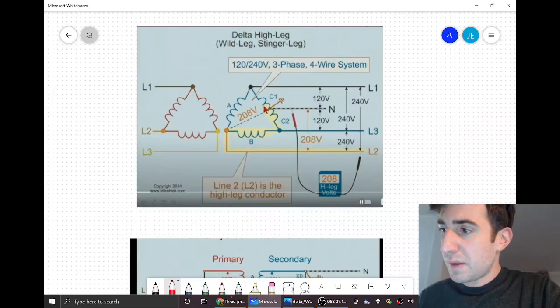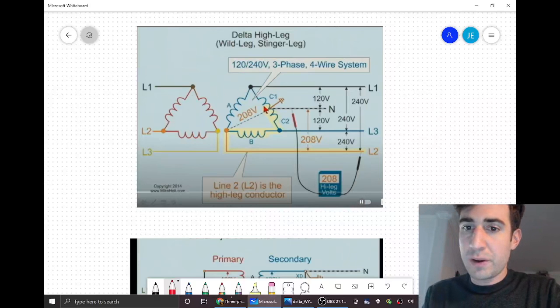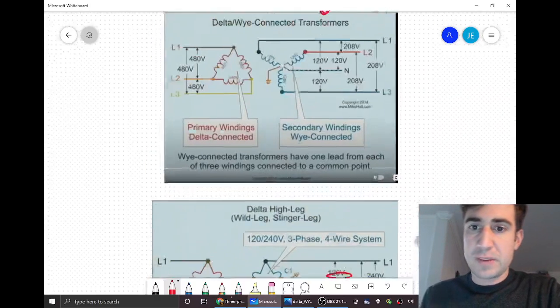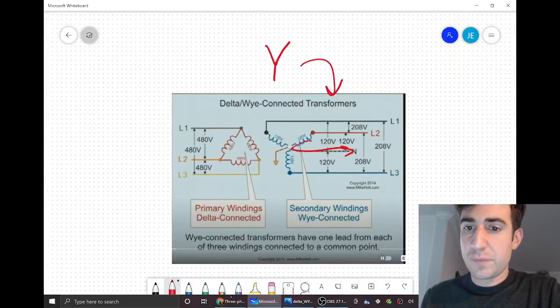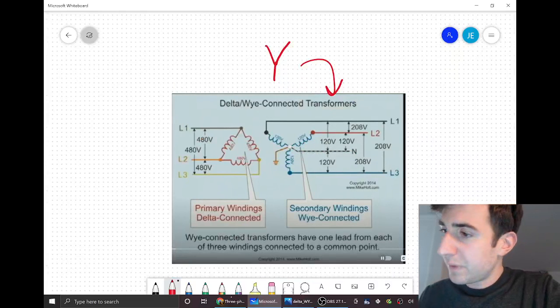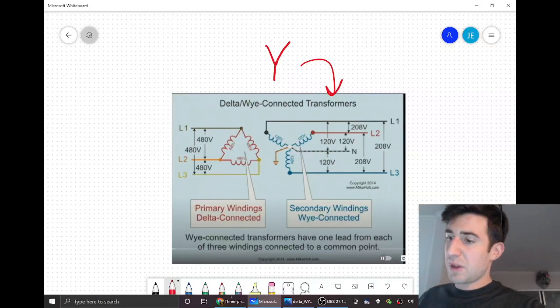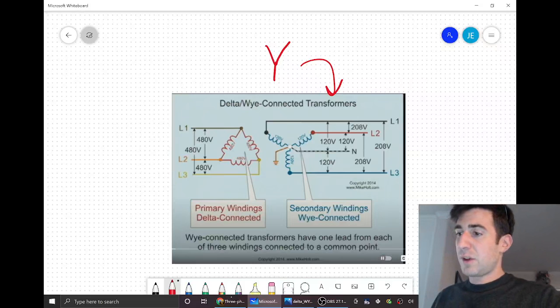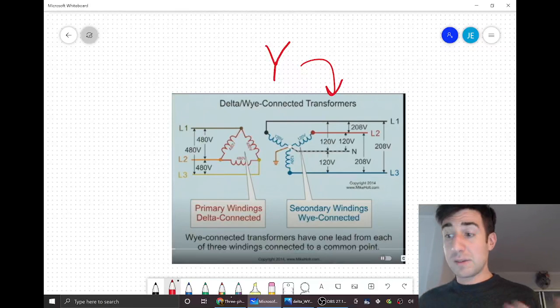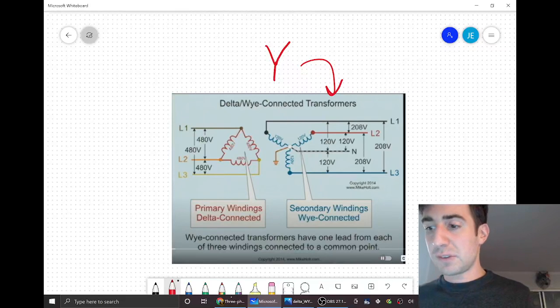And we don't want imbalances because the neutral wire here - oops, not that neutral wire, this neutral wire - can carry the unbalanced current. So design considerations have to really take those imbalances into consideration and make sure that we're seeing a balanced load from the place of supply by design. So that's some of the challenges that's incorporated.